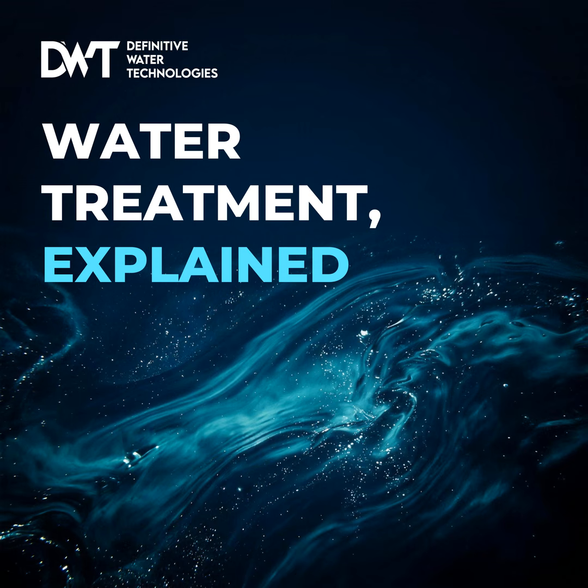But what happens when a gas bubble from that degrading hypochlorite gets sucked into the pump head? Oh, gas is compressible. Exactly. So the diaphragm pushes forward, but instead of lifting that heavy little ball, the energy is entirely absorbed by squishing the gas bubble. And then it pulls back and the bubble just expands again. Yes. The pump is running, clicking away, lights are on, but nothing is moving. It has silently lost prime. It's vapor locked. Wow. It's exactly like trying to push a syringe full of water, but there's a tiny balloon trapped inside. That's a great way to picture it.